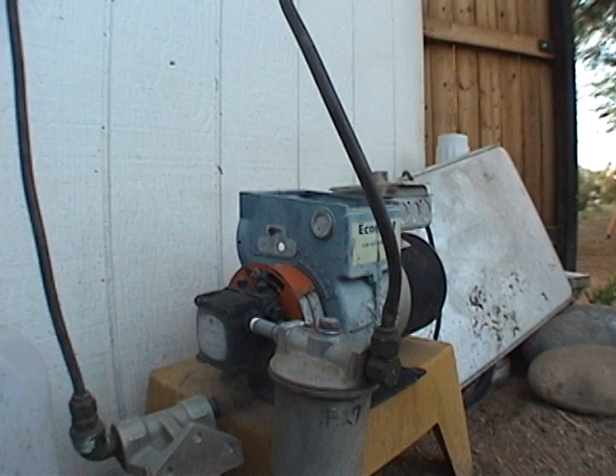It would have a nozzle port coming out the back with a 100 psi connection going into a nozzle which would shoot fuel into the furnace. But what we've done here is plugged off that connection, and we're basically using this oil burner pump as just an oil pump.